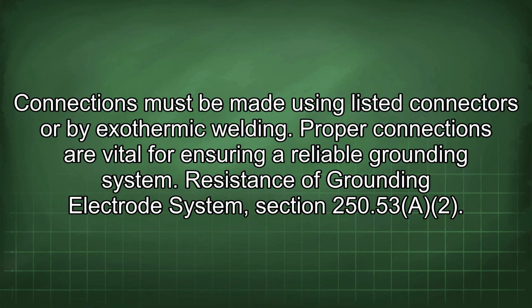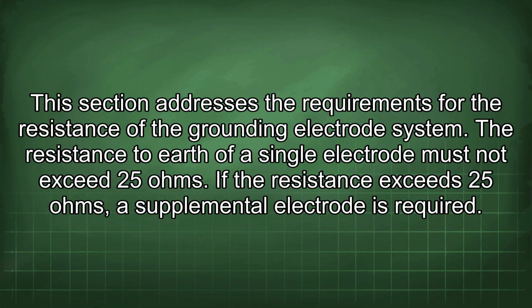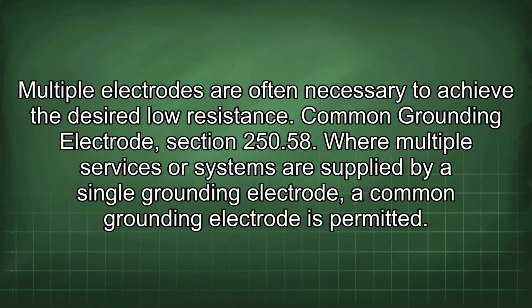Resistance of grounding electrode system, section 250.53(A)(2). This section addresses the requirements for the resistance of the grounding electrode system. The resistance to earth of a single electrode must not exceed 25 ohms. If the resistance exceeds 25 ohms, a supplemental electrode is required. Multiple electrodes are often necessary to achieve the desired low resistance.